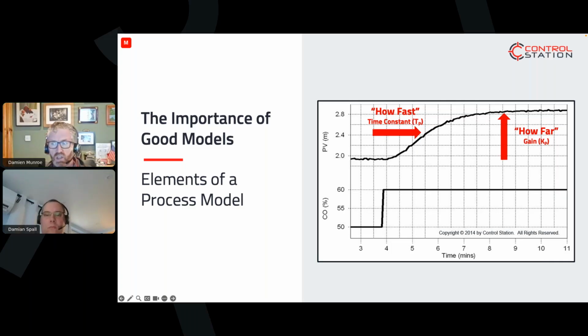Anytime you're looking at the data, think about the last trend you looked at. If you align your process variable in the upper chart and the output in the lower chart, we're looking for that relationship between these - this is what's called the process model. You see the three red arrows there, look at the right hand side, how far first of all: the output change in the lower chart relative to the PV response in the upper chart. So it's looking at how much the temperature or process variable moved when you move the output.